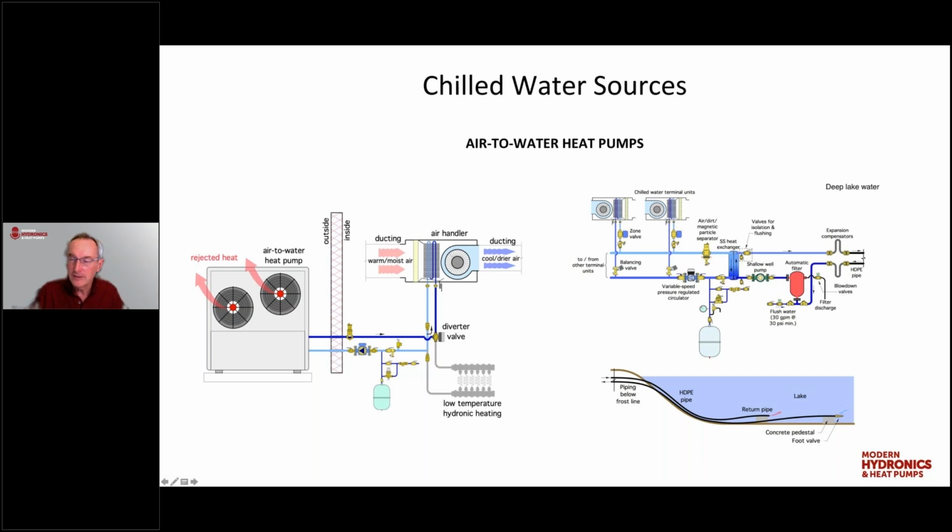What it does basically is it brings lake water in. There is an automatic filter making sure that we aren't sending sediment. First of all, we don't want our pickup line to be laying on the bottom of that lake. We want it up. But with storms and so forth, the water can get turbid, and this automatic filter would remove that. And you'll see we have an isolating heat exchanger here. So the lake water only comes through one side of that heat exchanger, goes back out, gets re-injected into the lake. The other side of that heat exchanger, in effect, becomes our chiller. It's our source of clean, chilled water. It's part of a closed loop system.